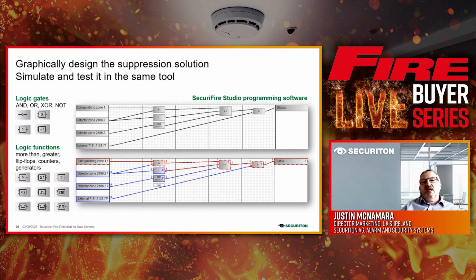One thing that sometimes gets glossed over is our ability to use the same software tool to provide the programming for our fire panel. We can sit in an office or studio beforehand, do all the programming, and get all the logic however we wish it to be. Then we can use that same software, that same code that's been written, to actually generate the logic on the panel at the site itself. It's a smooth, seamless process.